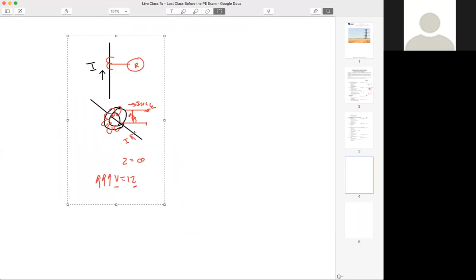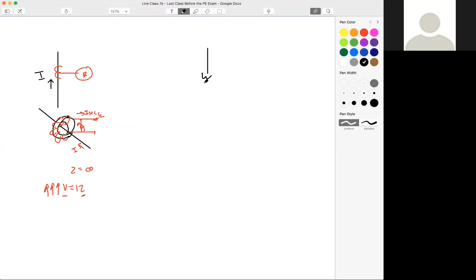So here's our CT. Why does that not happen on a PT or voltage transformer? Here's a regular power transformer. If this is a three-phase system, that transformer, if we were to draw it out, would look like that. We'll draw one phase of it to represent it. So if this is open, who can tell me what my secondary current is? If I have a PT or voltage transformer, what's my secondary current if this is open? It's 0, right?